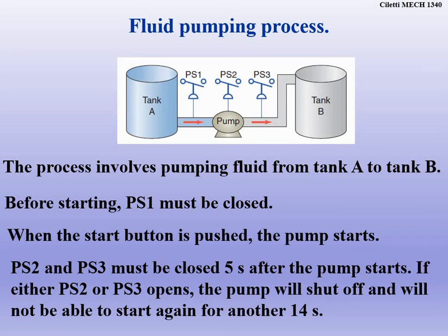If either pressure switch 2 or pressure switch 3 opens, the pump will shut off and will not be able to start again for another 14 seconds. Okay, so lots of different things going on here as we do this. So you might be able to pause this and write the scenario down and then look at the next slide here as we got this going on.